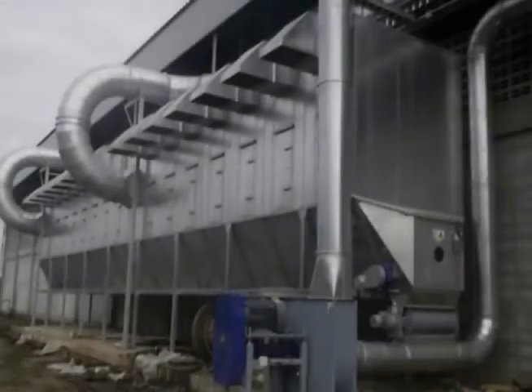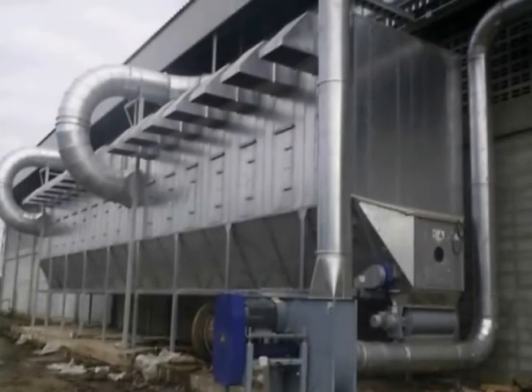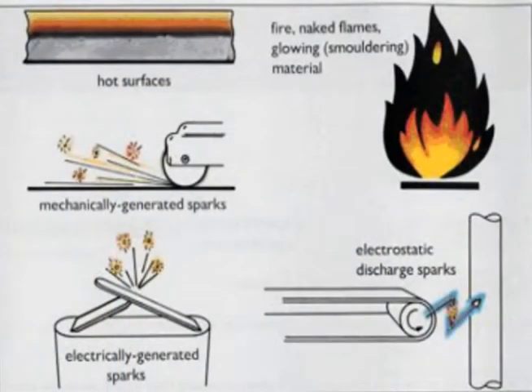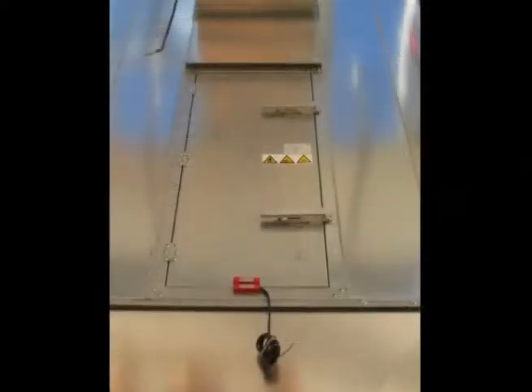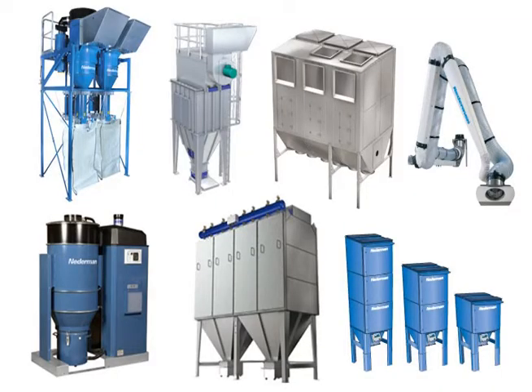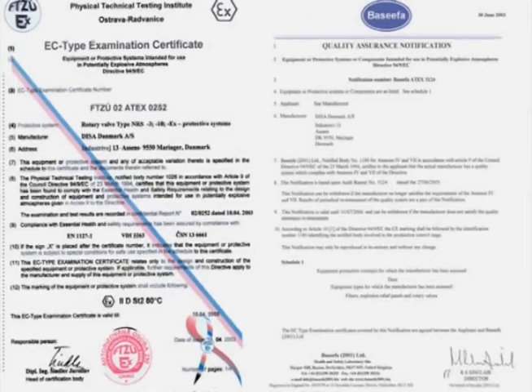This filter system is similar to many other systems in the wood industry. Filter systems for other industries with explosive dust shall be based on the same basic principles: remove dust at the source and keep the process controlled; remove ignition sources; reduce the risk of container deflagration with explosion vents or similar measures; reduce the spreading of explosions with barriers and safety systems. A wide product program covering all types of industrial ventilation, many certified under ATEX for dust and/or gas, gives you optimal systems.